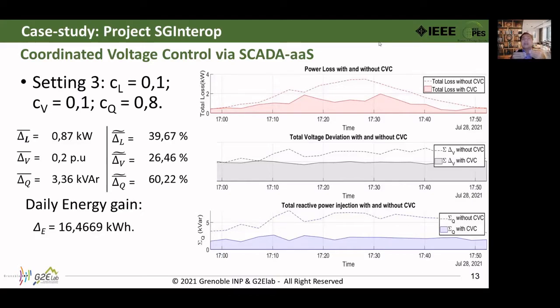In my opinion, it may relate to the fact that reactive power from the renewable energy was required for the regulation of voltage control, in order to satisfy the voltage constraint. So that's why we were not able to reduce a lot in terms of delta Q. However, a 60% improvement with respect to the case without our CVC is already considerable. In general, the CVC algorithm allows the grid operator to avoid the loss from 16 to 23 kilowatt-hours per day as a function of the configuration.